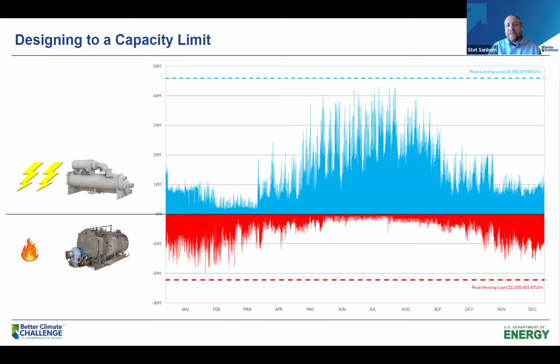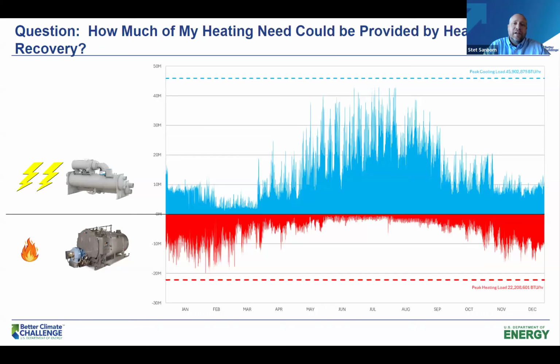So this is a curve that has the hourly cooling load profiles on the top and the hourly heating profiles on the bottom. For this building, you'll see it's got an electric chiller running the cooling, and you see the gas-fired boiler. The worst thing that we see is when folks say, I just want to replace that boiler with something. Oh man, there's a lot of opportunity already for heat recovery to offset a ton of your energy use in the building. So the question that you want to ask your auditor is, how much of that heating load, and heating load's the one that's often hardest to do with a heat pump, how much of that heating load could be provided through heat recovery?